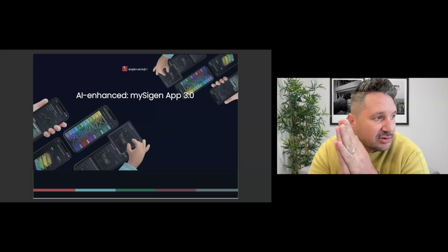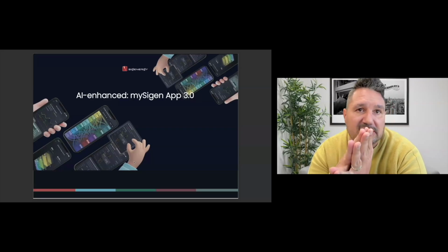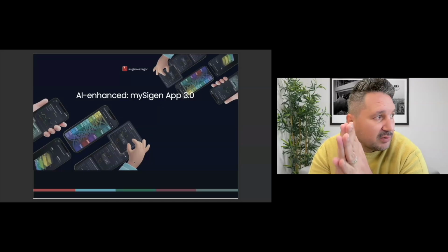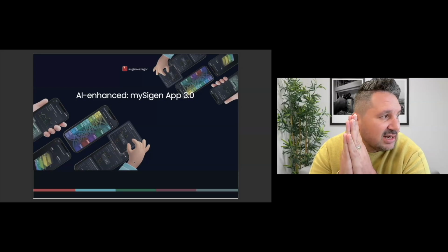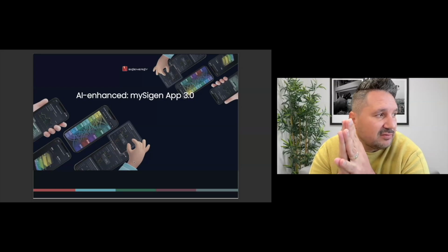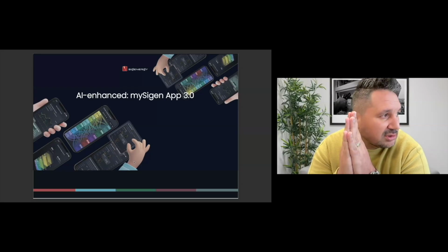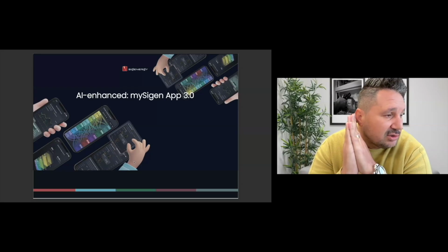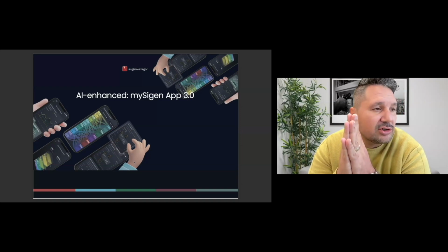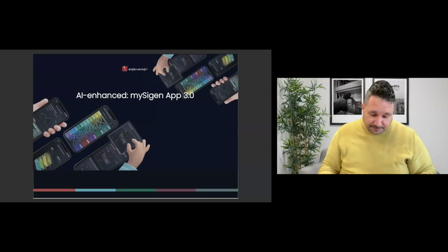It also has a plug-in to the ESP app, which then preps the battery should you be using it as an arbitrage or time of use saving method. The moment load shedding or any power outages is announced, the battery will charge itself automatically to make sure that you do not run without power. It will also not aggressively charge the battery to full capacity. It will only charge for whatever stage of battery would be needed, and it will charge at the rate that makes sure that the battery is always protected and not being overcharged.